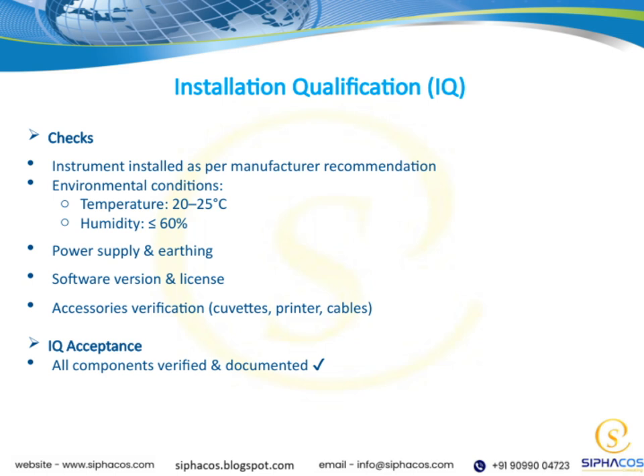We also need to check the power supply and earthing. Proper electrical connections and grounding are vital for safety and for preventing any electrical issues that could affect the instrument's operation. Then, we verify the software version and ensure that the correct license is installed. This guarantees that the instrument is running the latest, most secure software and has all necessary permissions.